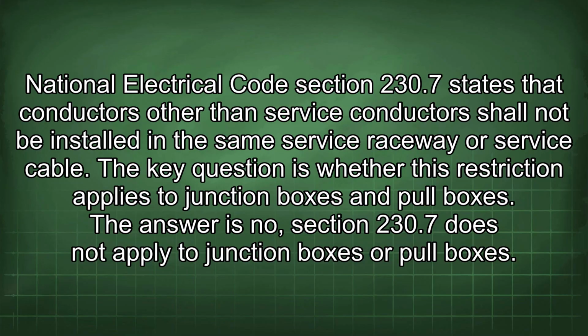National Electrical Code Section 230.7 states that conductors other than service conductors shall not be installed in the same service raceway or service cable. The key question is whether this restriction applies to junction boxes and pull boxes. The answer is no. Section 230.7 does not apply to junction boxes or pull boxes.